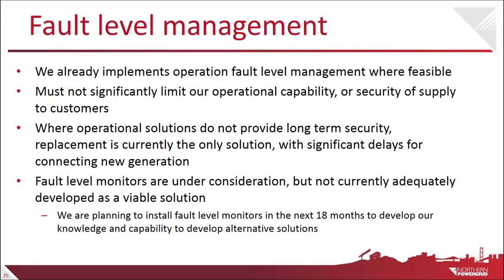So fault level management, we already use, where we can, operational fault level management where it's feasible, and a lot of our grid supply points already operate in some split configurations where we have enough transformer capacity to still maintain security of supply to customers. But any operational solutions that we use, it is important that we don't impact on our capability to operate the network for planned maintenance outages and for faults, and that we don't affect significantly the security of supply to our end customers.